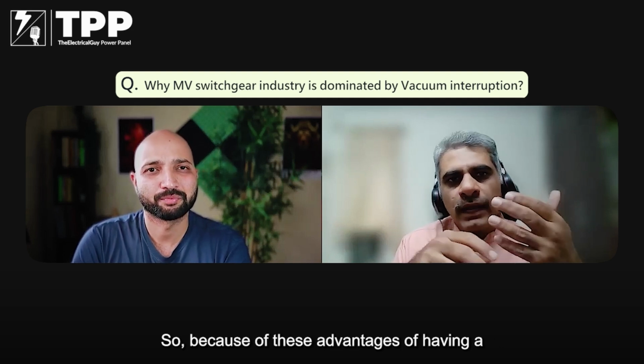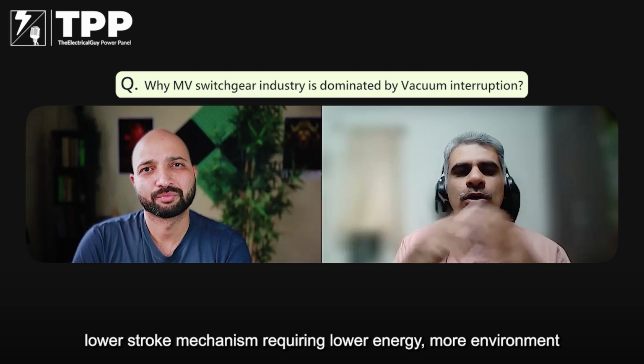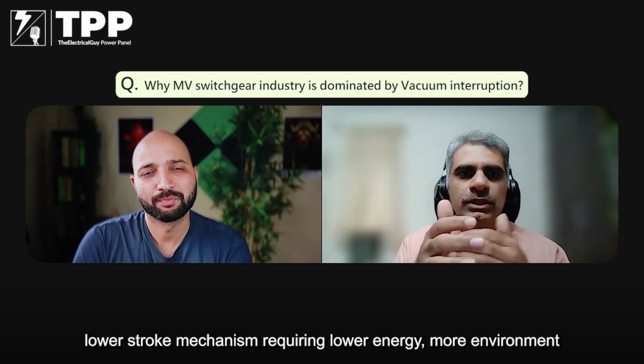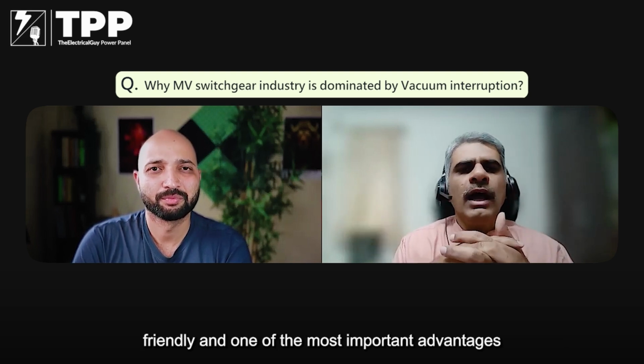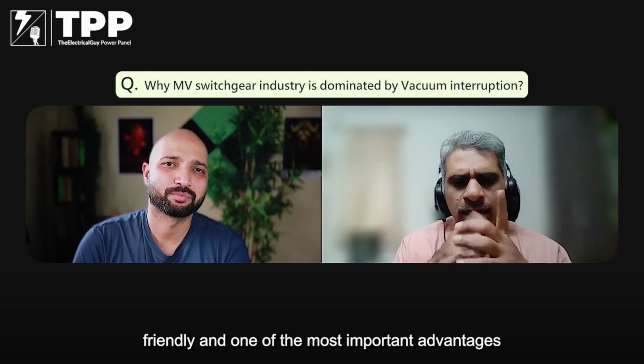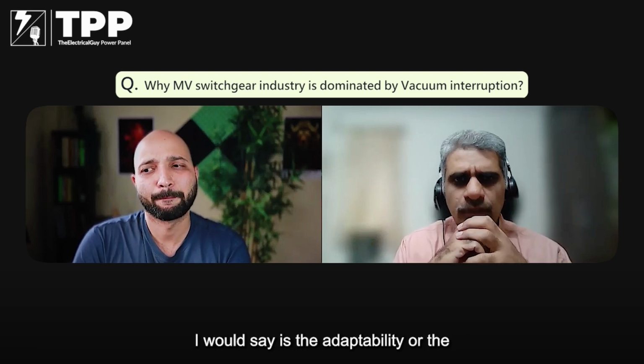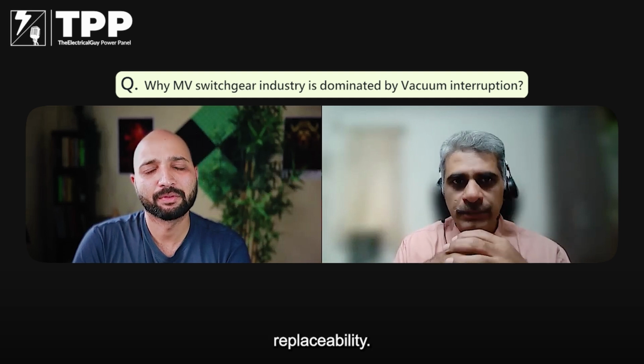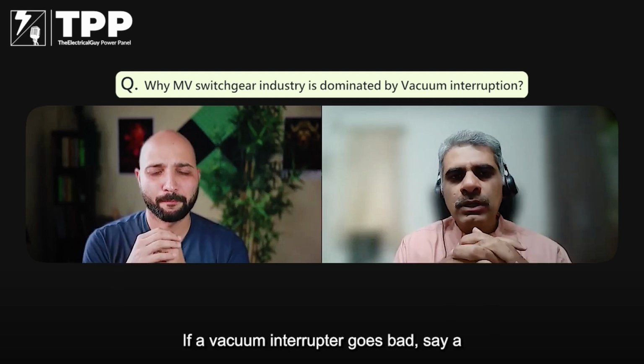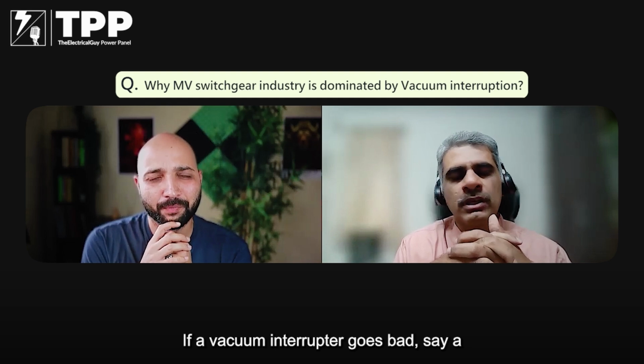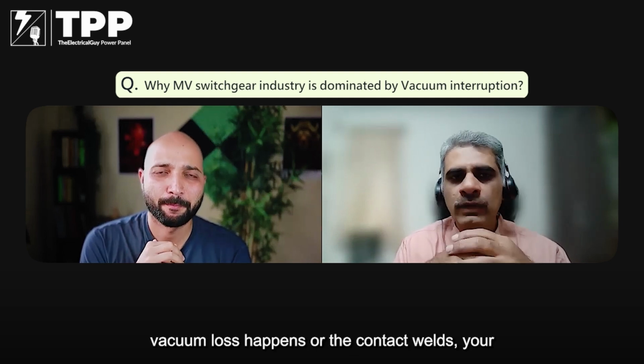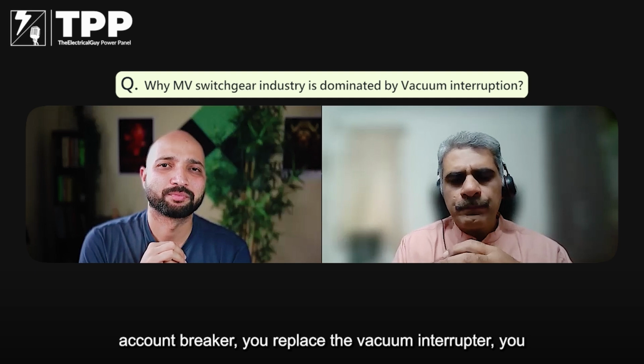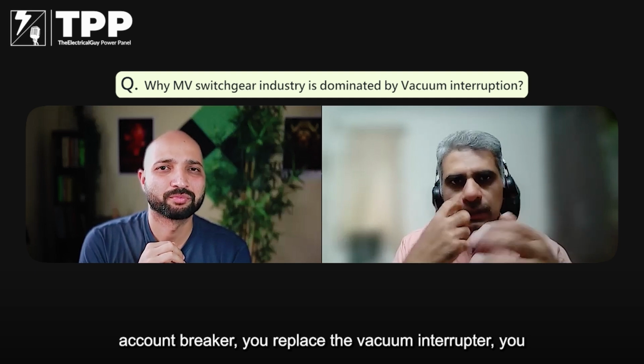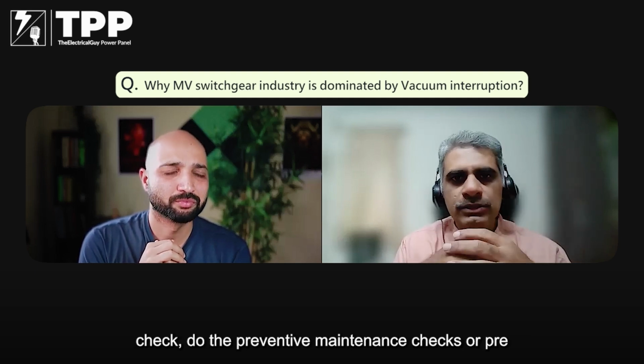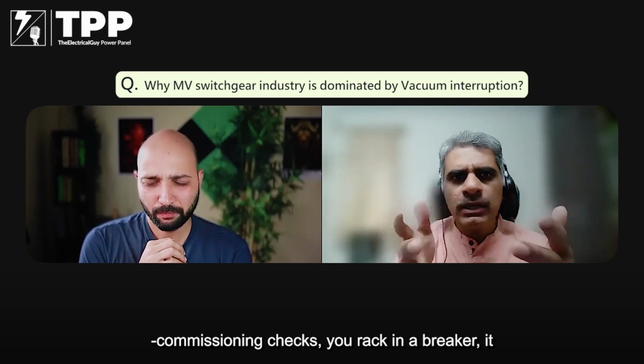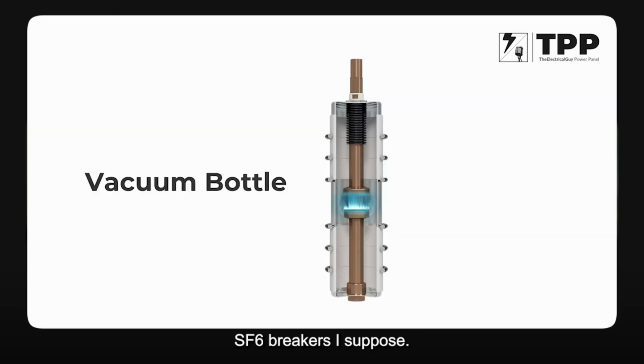So because of these advantages of having a lower stroke, a mechanism requiring lower energy, more environment friendly, and one of the most important advantages I would say is the adaptability or the replaceability. If a vacuum interrupter goes bad, say a vacuum loss happens or the contact welds, you rack out a breaker, you replace the vacuum interrupter, you do the preventive maintenance checks or pre-commissioning checks, you rack in a breaker, it's ready. It's not the same in case of SF6 breakers, I suppose.